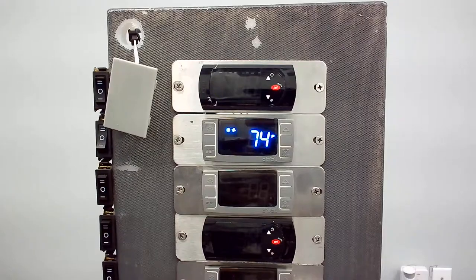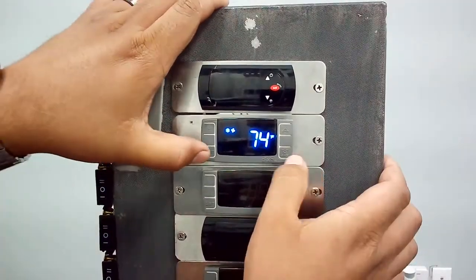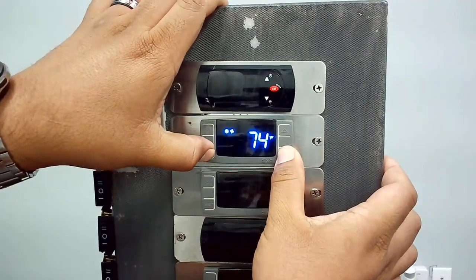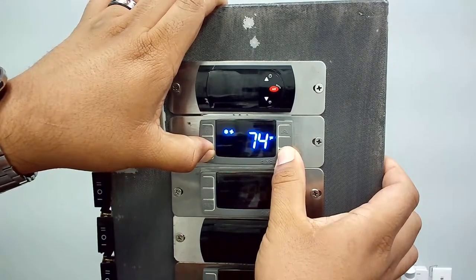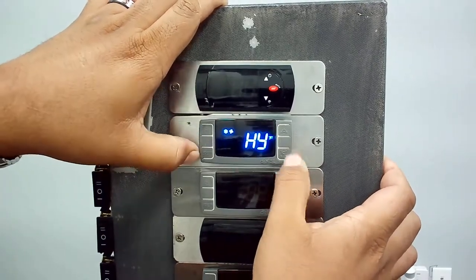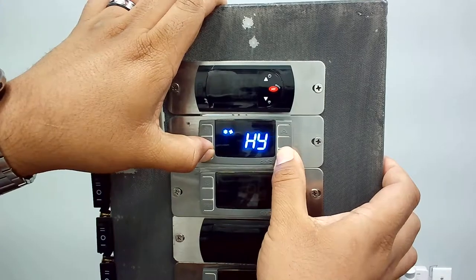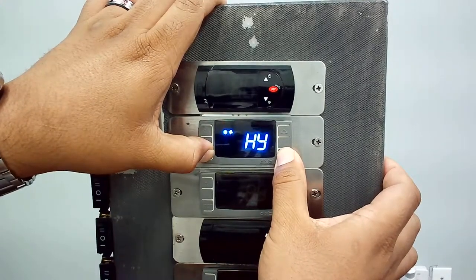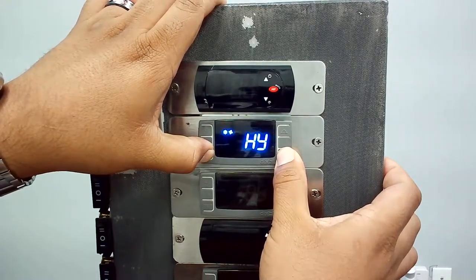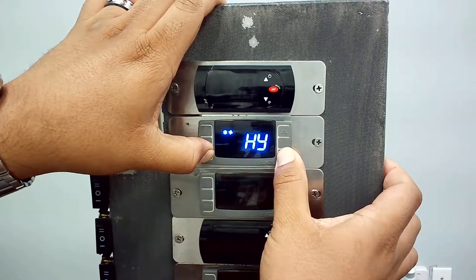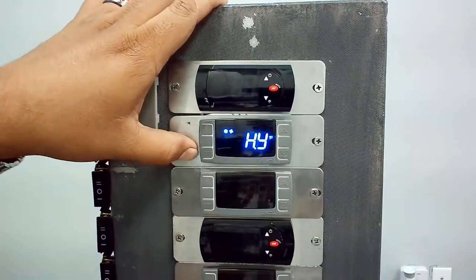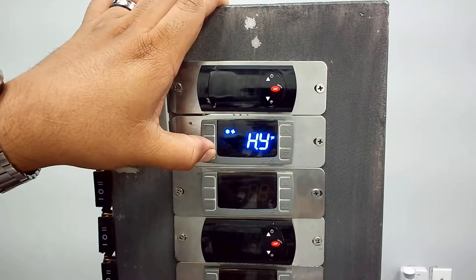So let's get started. To get into the settings, we're going to be holding down the set button and the down arrow together until it says HY. Once we're there, you let them go, hold them down again, this time for about 10 seconds. It'll say L2. And then once you let go, it'll say HY. So once you're there, you're going to use the set button to navigate.